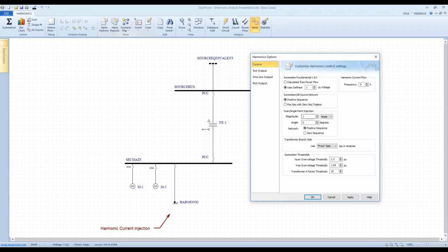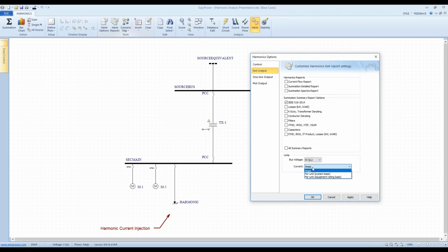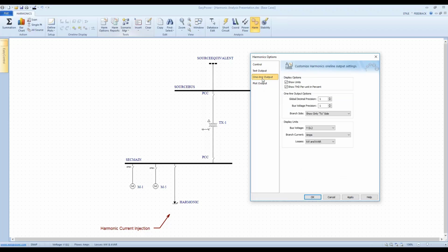So with that being said, it's also important to realize that we also have per unit here too. So the current flow in the text outputs can be either in amps or in per unit. And remember, it's going to be per unit on a system base, and then again per unit on equipment rating base. Okay, the rating of the conductor, the rating of the transformer, etc. I typically always use amps because I can relate to amps more than I can relate to per unit. I think 1 per unit is difficult to relate to when it comes from a harmonic analysis standpoint.